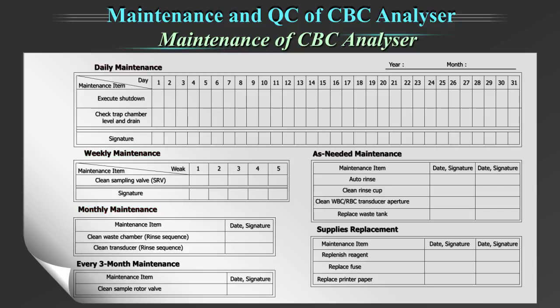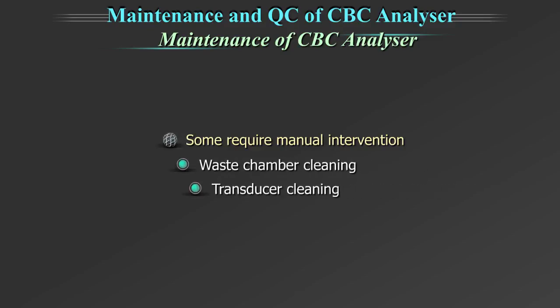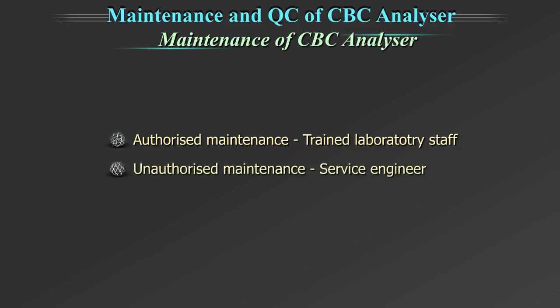You can see a maintenance chart of KX21 on the screen. The important weekly maintenance includes cleaning of the sampling valve. Some maintenance are performed automatically by the machine on executing commands, whereas some require manual intervention like waste chamber cleaning and transducer cleaning. Some maintenance are authorized for trained laboratory staff, while some are unauthorized maintenance which are done by the service engineer of the company.